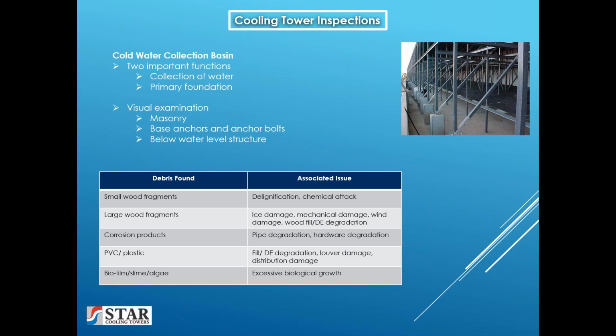And the structure below the water level, obviously this is a time when the basin is empty and you have an opportunity to inspect the structure that's normally submerged in the water. Also, the screens that separate the basin from the pumps should be inspected to make sure they're in serviceable condition and to identify any debris that might be in the screens that might identify problems in the tower, such as maybe fill that's coming apart or wood pieces from deteriorated structure. Sometimes these can be very telling.